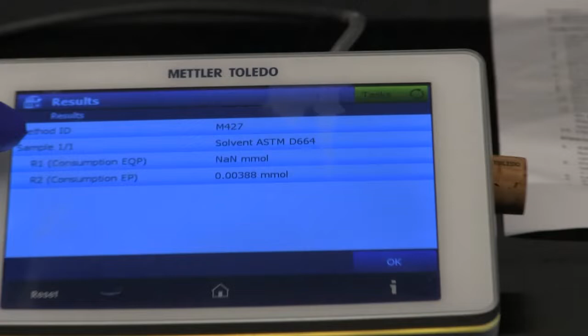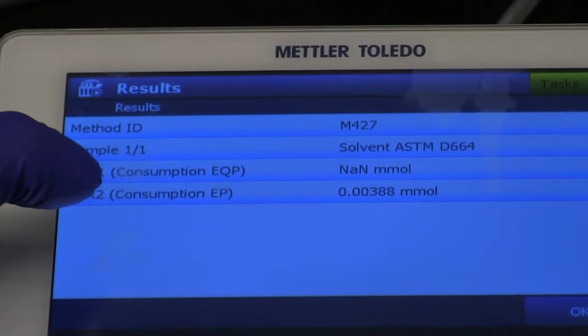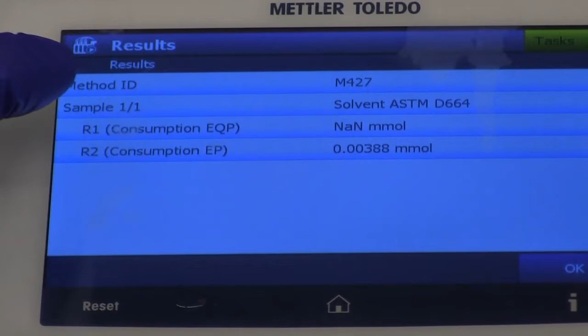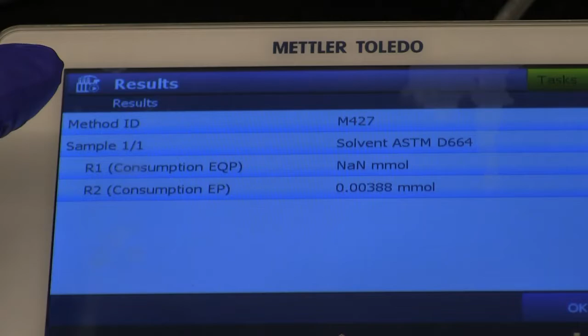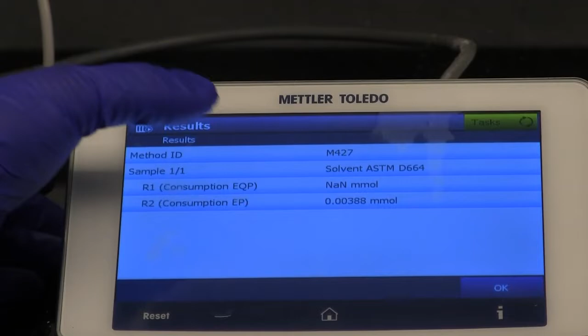You need R1 to be not a number, which is your equivalence point, and R2, which is the end point, to be less than 0.2, or ideally less than 0.1 millimole. If this is the result you're getting, then you are good to go. If not, you probably need to redo your reference measurement or blank acid number. But since it's good, we can continue. So I click OK.